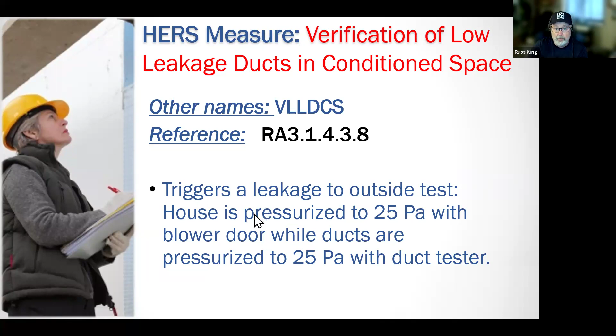So, verification of low leakage ducts in conditioned space. If you trigger that HERS inspection, make sure that you're aware. Talk to the HERS rater and say, is this even going to be doable in this house? Okay. The target leakage is only 25 CFM. That's a very small number, regardless of tonnage. All right. It's highly recommended that the HERS rater do a pre-test before the ducts get covered up, what's called a rough test. So they'll go out when the ducts are installed, but maybe not the registers and maybe not the equipment, and they can do a rough test and identify any leakage with a smoke machine, and seal all the leaks before all that duct gets covered up with drywall. Because if they don't pass a test after the ducts are covered up with drywall, it can be really tricky to fix that problem.